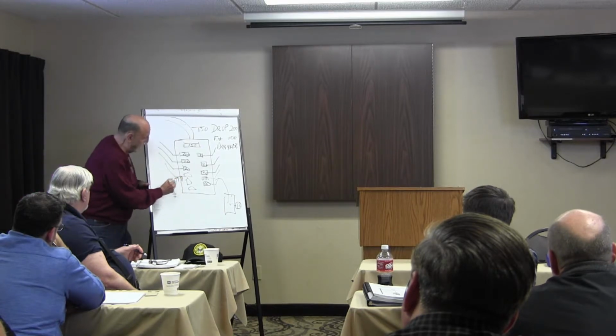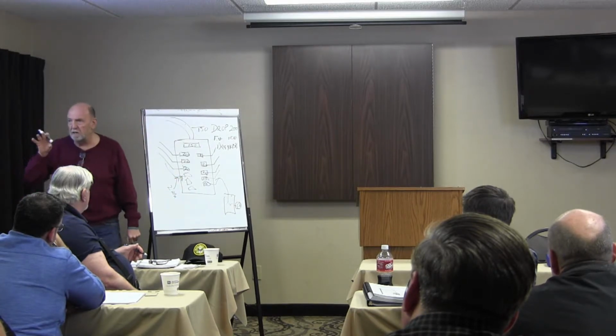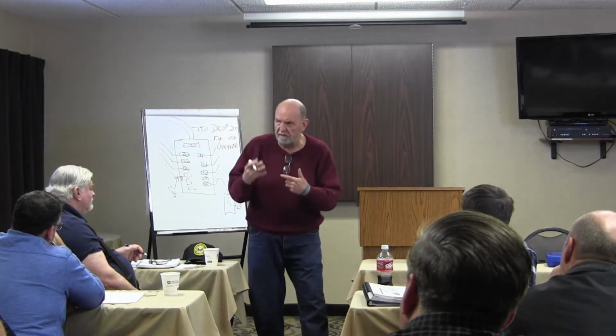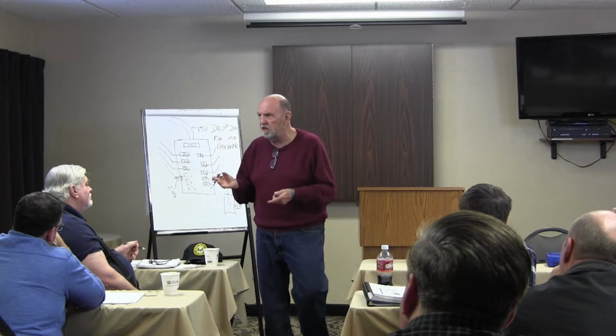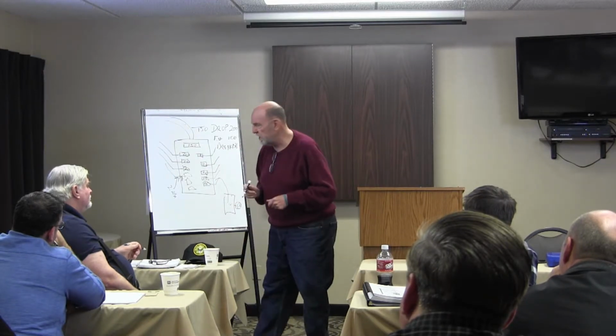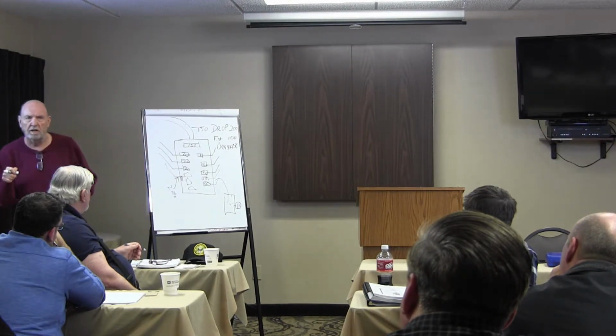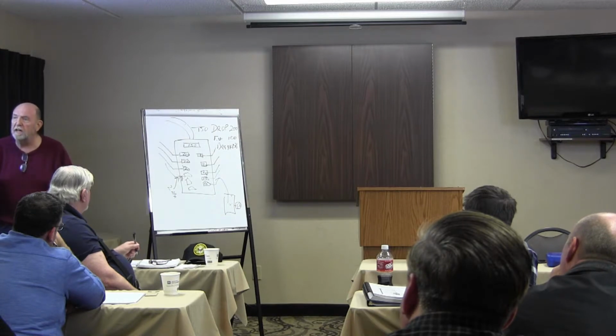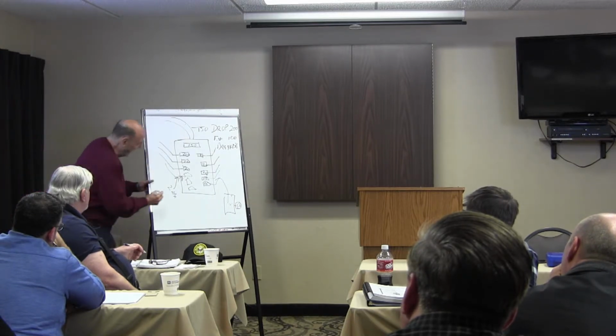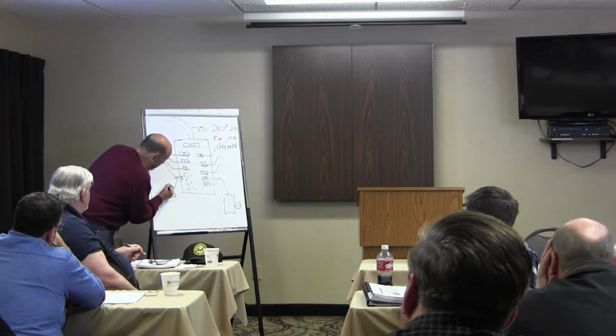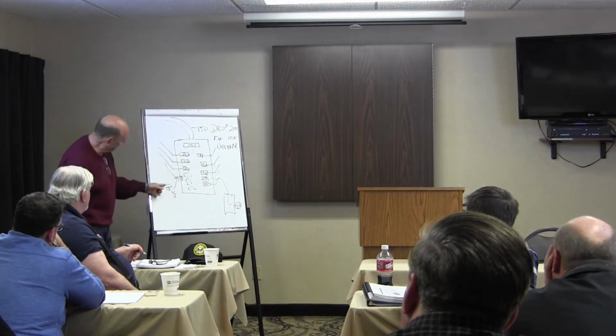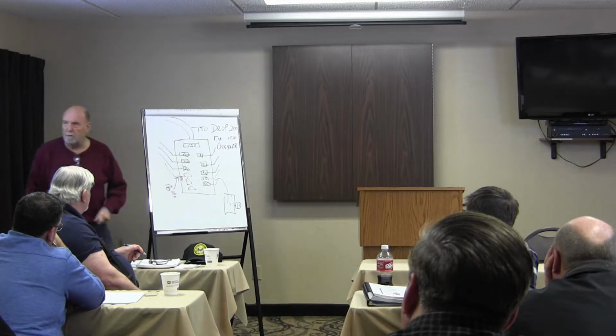2 amps. I've done this at my brick and mortar school. I had these Mr. Coffee electric coffee pots, when we had a CEU, and I had 4 coffee pots on the table on a 15-amp breaker, and it operated 3 fine. I plugged the 4th one in and it popped. That tells me the 15-amp breaker was working. It also tells me those things draw 4 amps. So I get 4 coffee pots on this circuit, and that breaker's supposed to break, correct?